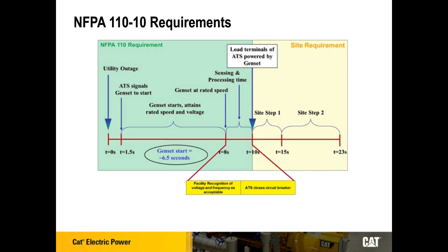Starting at the left side of the timeline, at the beginning there's the utility outage, and it takes up to 1.5 seconds for the transfer switch to decide that the utility power is not present and not coming back quickly. At that point the ATS signals the generator set to start. It will then attain rated speed and voltage in about 6.5 seconds, and then we have up to 2 seconds for the transfer switch to qualify the generator set as a valid source of power and transfer the load onto it.